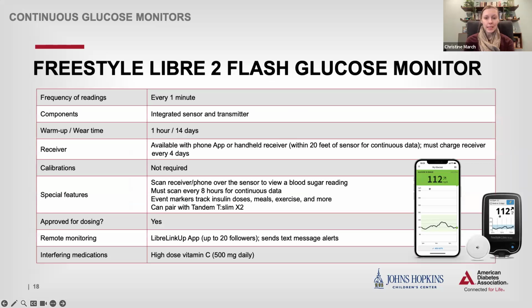Now, moving on to the Freestyle Libre. The original Freestyle Libre was actually considered a flash glucose monitor, meaning you would scan it with a device to get the sugar reading. The Libre 2 is sort of a hybrid between a flash and a continuous glucose monitor. This can give you a reading up to every minute, includes an integrated sensor and transmitter, and the warm-up time is 1 hour with 14 days of wear, so longer wear time than the Dexcom. This also has a proprietary receiver, which you can see pictured here, or you can use their phone app.